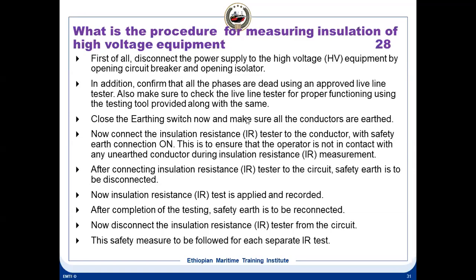After completion of the testing, you have to put the earth back again. The breaker earth switch has to be closed again. Then disconnect the insulation tester. The safety measures are to be followed for each separate IR test. So this is exactly the testing procedure of a generator stator winding insulation. As I told you, first you need to switch off the power, take out the breaker, make the ground switch on, then connect your insulation tester, remove the ground switch, measure the resistance, put the ground switch on and finish it. That's the way it has to be done. This is the procedure for measuring insulation of a high voltage equipment.